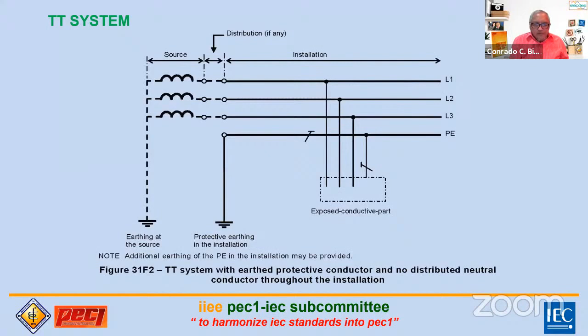Then here we have a TT with earthed protective conductor and no distributed neutral. So wala naman siyang neutral. Tulad kanina, merong neutral na nakakonekta. So meron siyang 3-phase 4-wire, meron siyang line to neutral load. So ito wala siya. So again, kailangan na naman dito ng detection para mag-trip yung protective device mo. So it's very important kung saan mo dapat i-apply itong TT system.